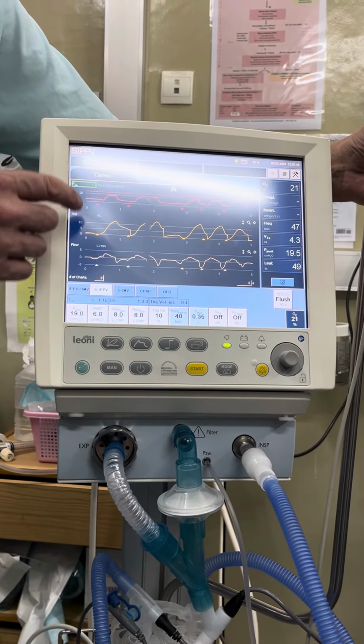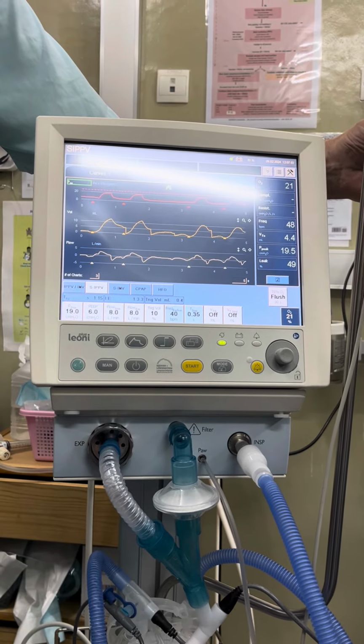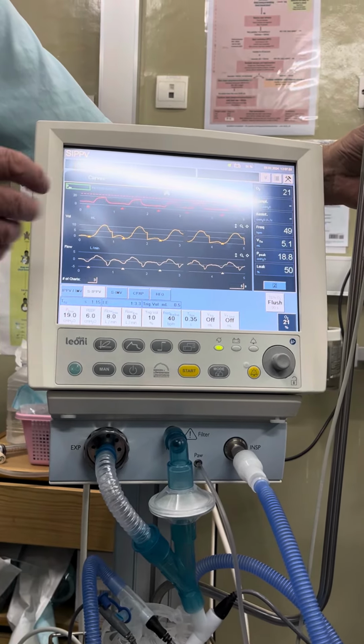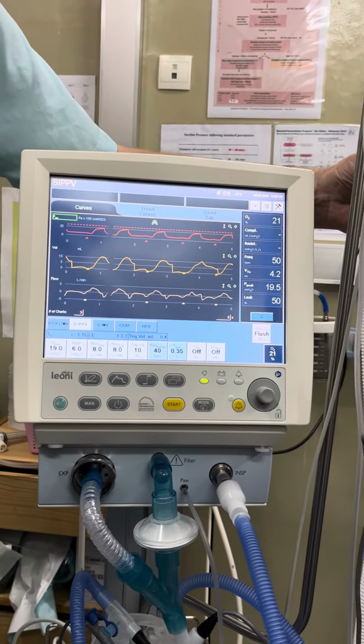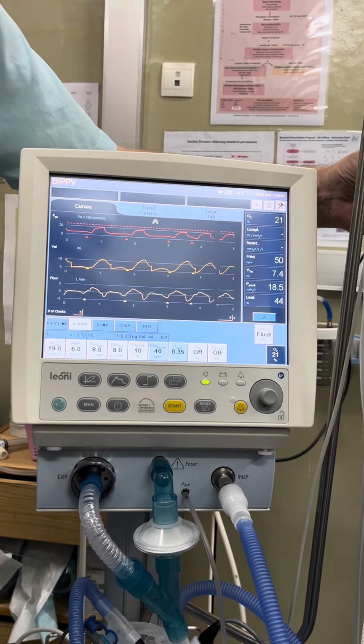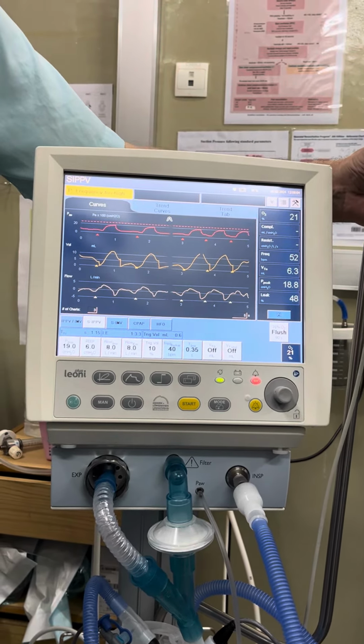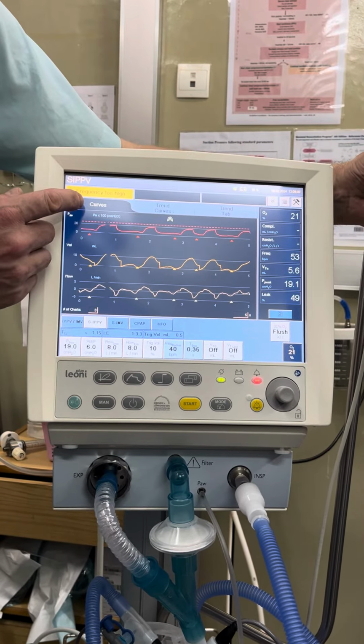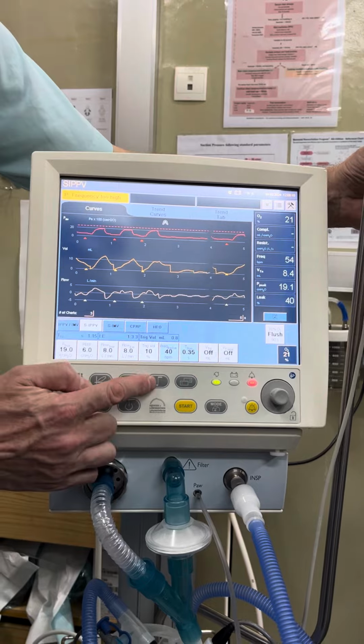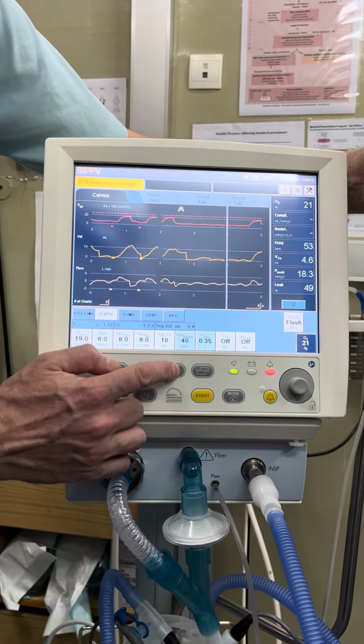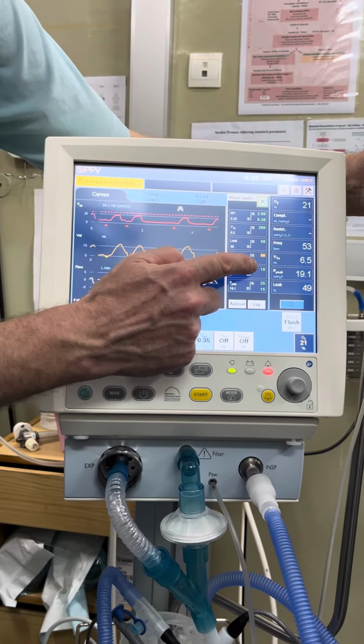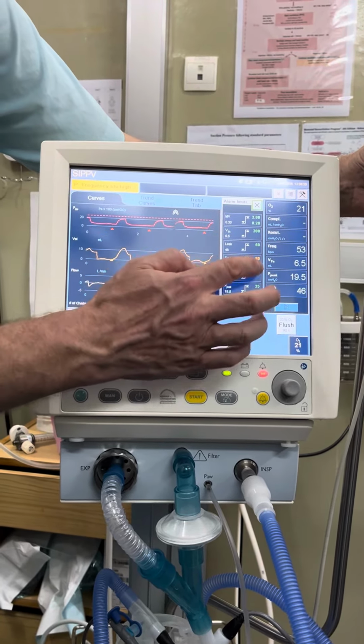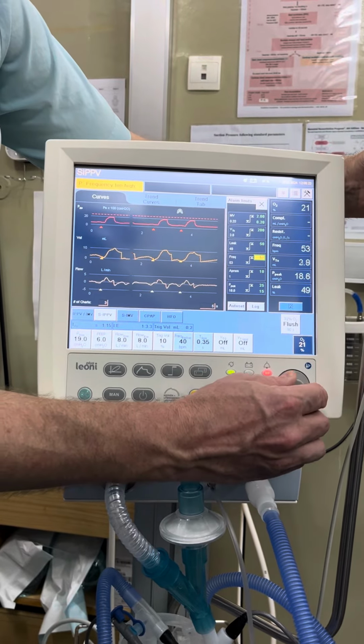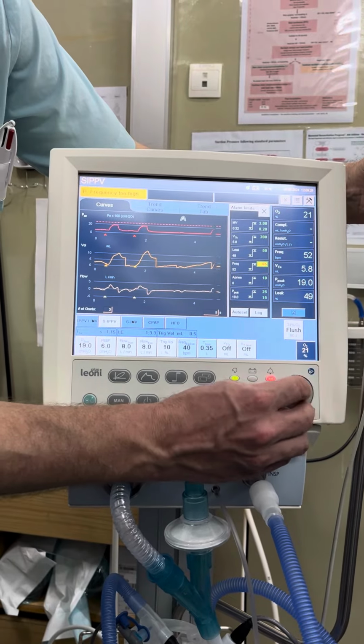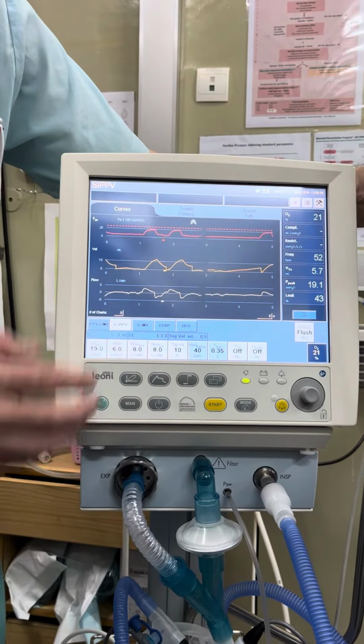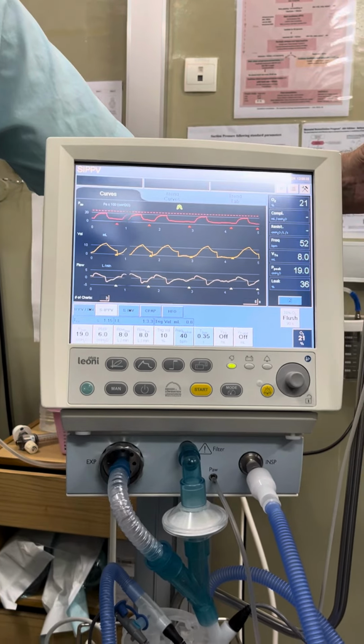As soon as the machine thinks the patient is breathing too fast, it will alarm. Maybe you should change the setting, for example, from 40 to 60 per minute, if you understand. So frequency too high. What shall we do about that? We need to go to the alarm limits right here. We find the frequency, yeah, there it is. Patient is breathing more than 50 per minute. So we need to turn up that alarm limit. It's turned up to 65. The alarm disappears. Okay?